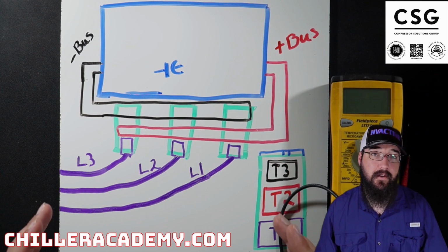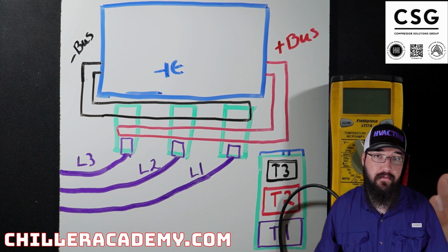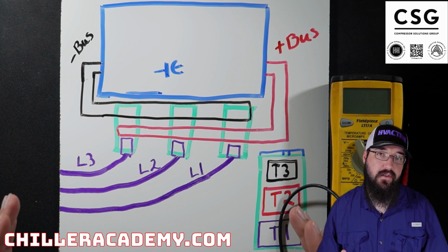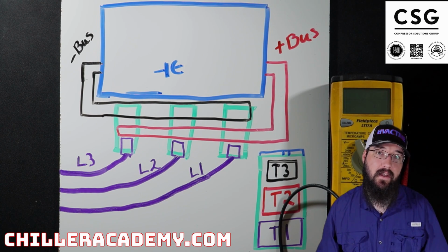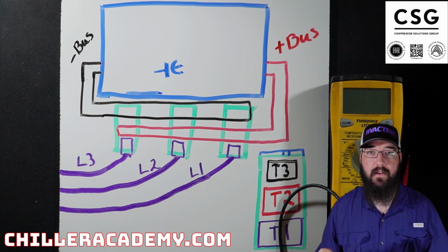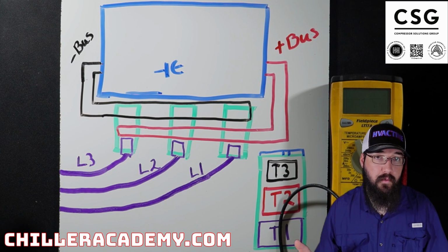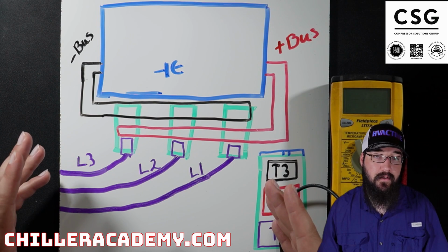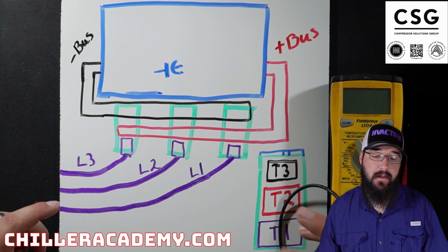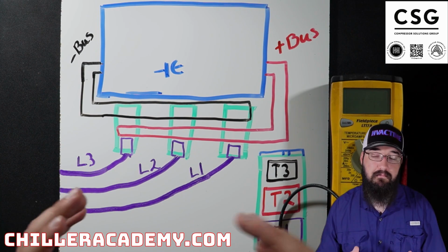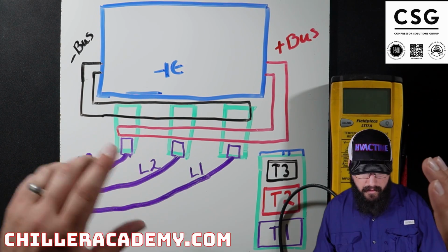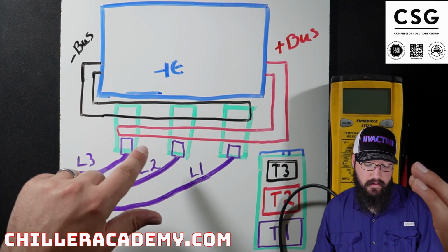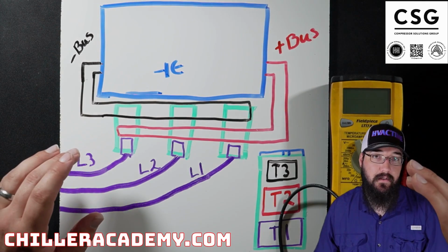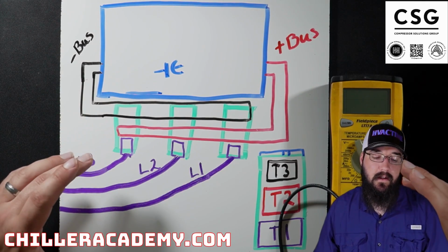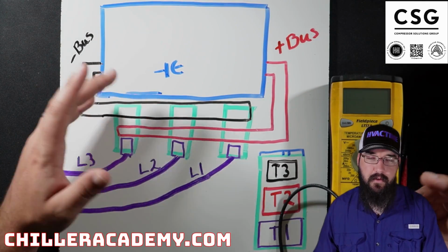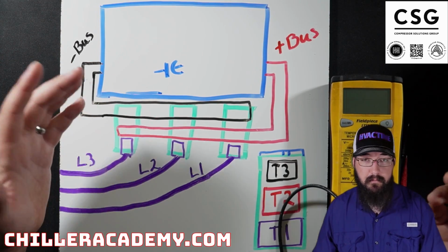So this does not guarantee that the SCR is fully functional and everything's okay. This just states that the internal silicon hasn't had a direct or obvious failure or internal short. There are two big reasons why I'd ever need to check this in the field. One, if I am popping my fuses, something's going on. More than likely, in my experience, either one of these SCRs or this DC bus has failed. Typically, it's an SCR. By DC bus has failed, that could mean a capacitor is blown. And I've had both happen.